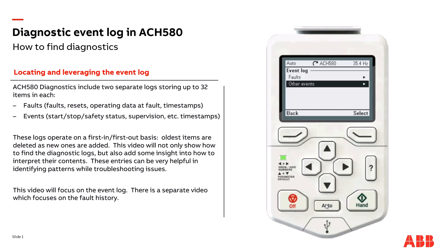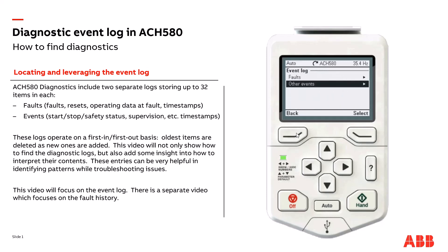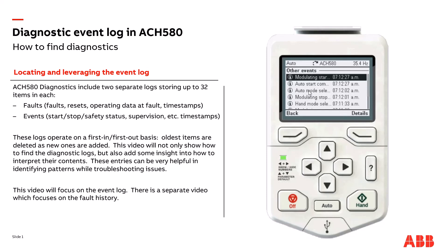Let's go back out and now transition to Auto. I don't have a run command active at this moment, so it's a simple transition from Hand to Auto — modulating stops and we're now in Auto mode. Now let's throw a start command by closing DI1 on the demo case. We can see that we've started in Auto mode: Auto mode selected, Auto start, and modulation started.